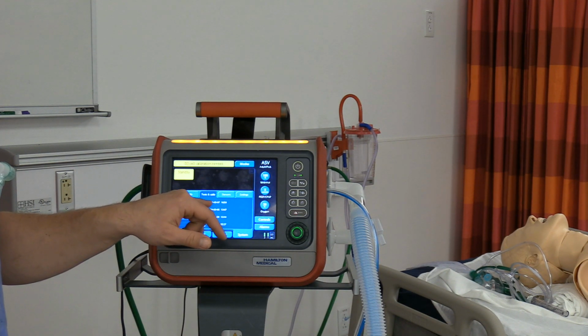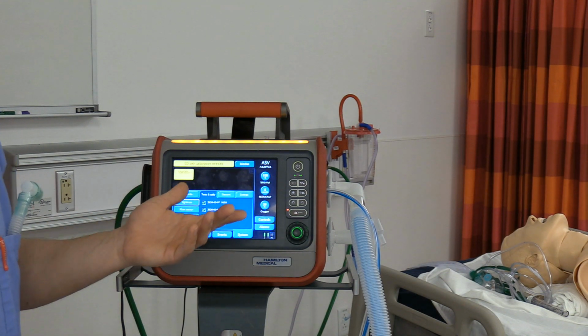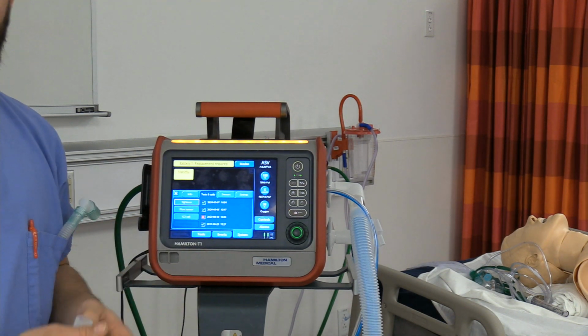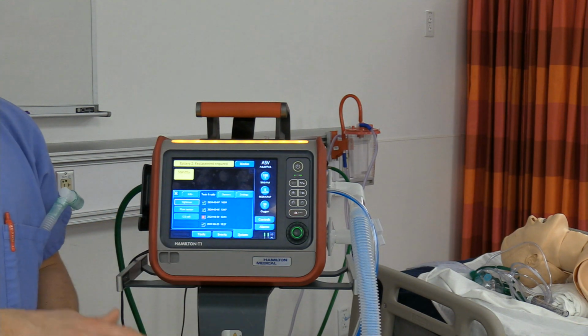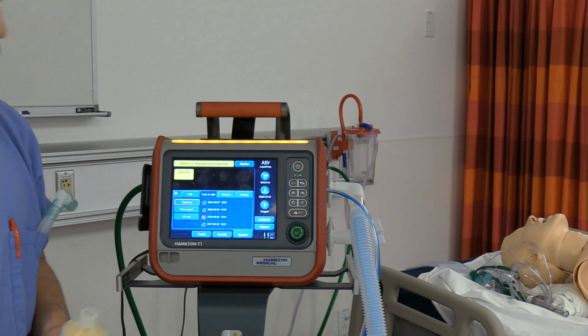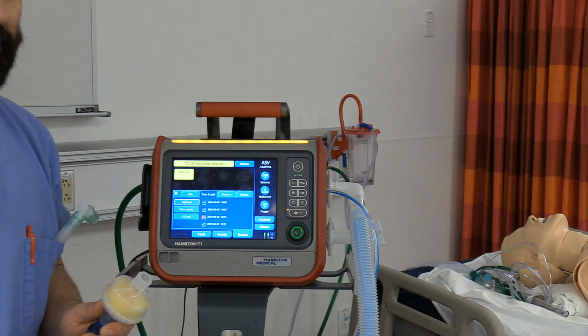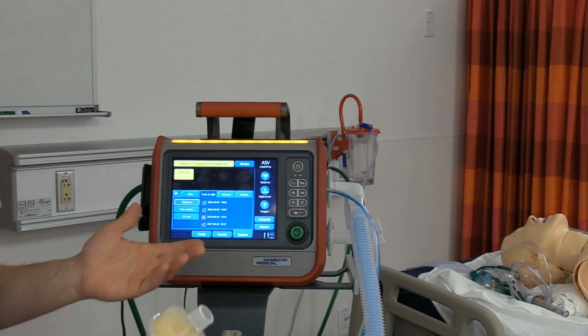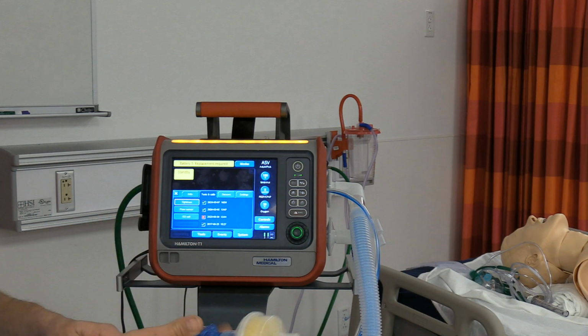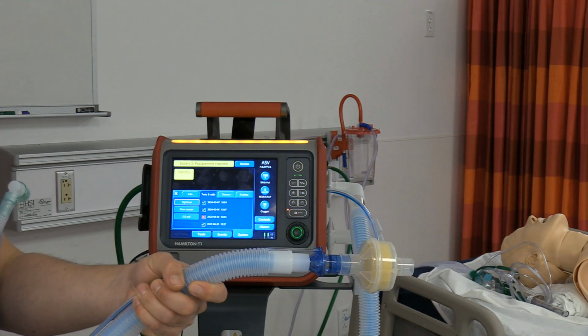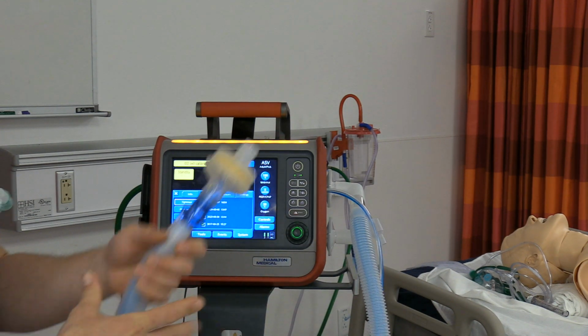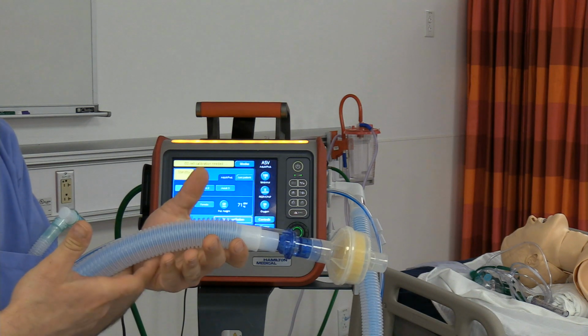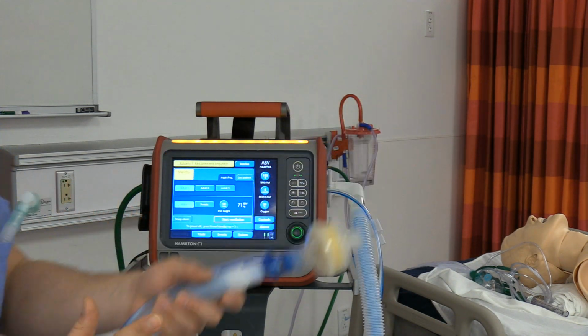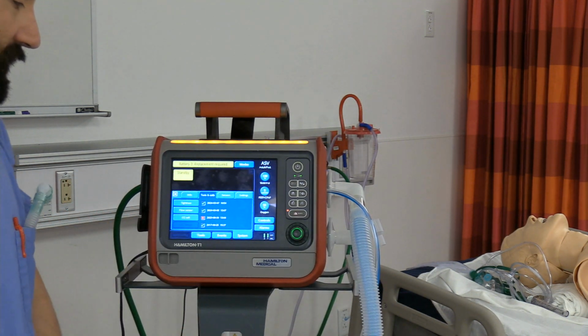So in this particular case, a lot of times we're doing this before you're actually going to a patient room, we would at least have some means of making sure that, hey, this was done at this time. Some hospitals are going to have a sticker or a cover that goes over this afterwards, just so the end user knows that this is completed. So tightness test, making sure our exhalation diaphragm's good, our circuit's good, we don't have any leaks, and compensating for that lost volume from circuit compliance. Making sure our values are accurate.